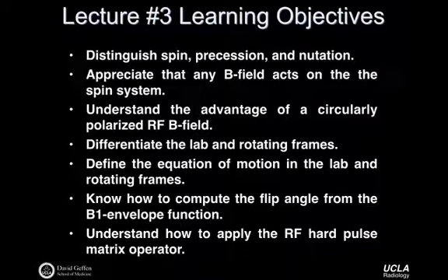We talked a bit about circularly polarized RF fields and compared them to linearly polarized fields. What was the main advantage of being circularly polarized? Lower SAR, right? So less patient heating. If we want to tip the spins over by 10 degrees, we can do that with less energy if we use a circularly polarized field.